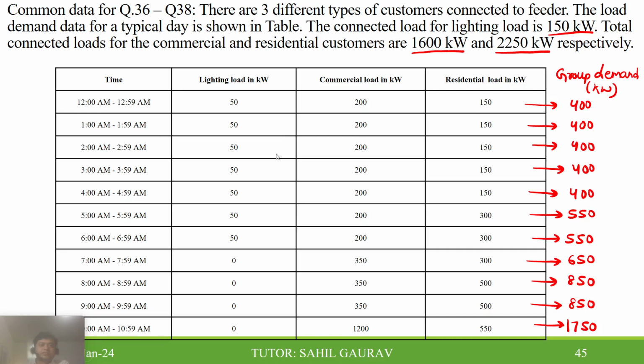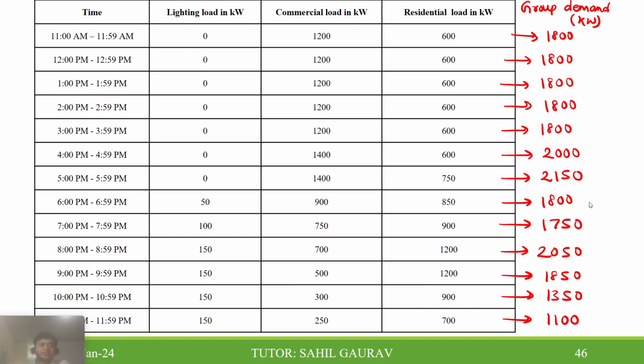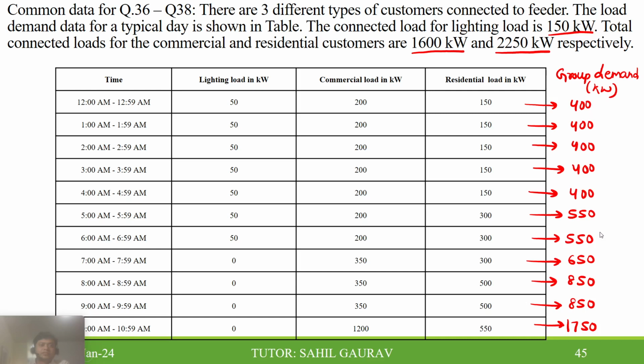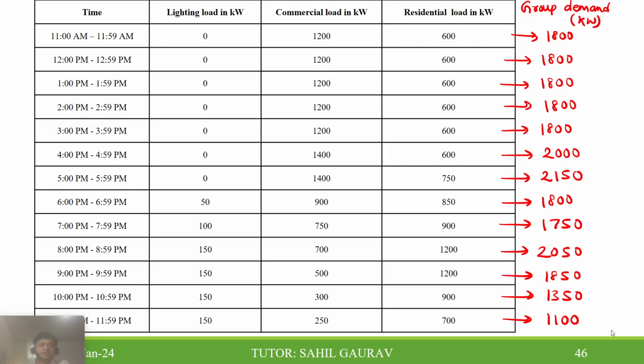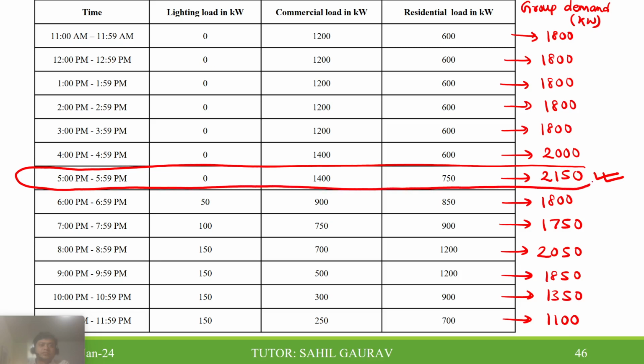You just sum during each time, and then you can see the maximum group demand. You can see the table here: 400, 400, 400, 550, 650, 850, 1750, 1800, 2000, 2150, 1800, 1750, 2050, 1850, 1350, 1100. So this is, yeah, 2150. Very nice. So this is the group peak demand. You just have to note down this row. This type of problem is given in the assignment but has not been covered in the class. I think in the discussion forum we can provide the material.